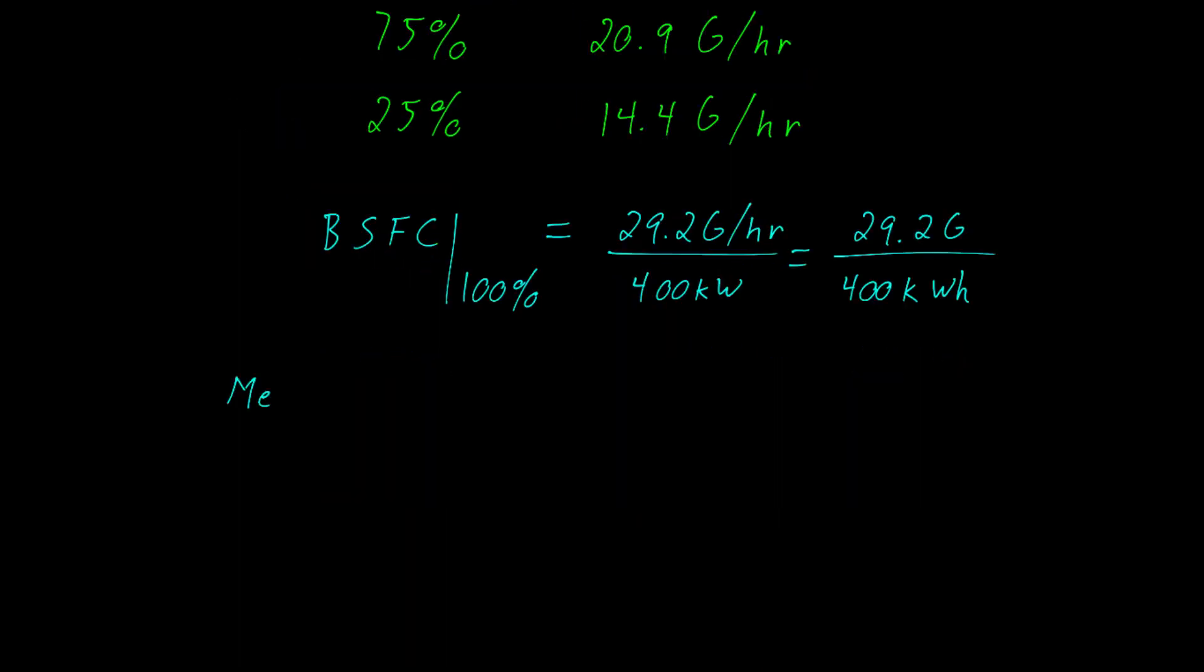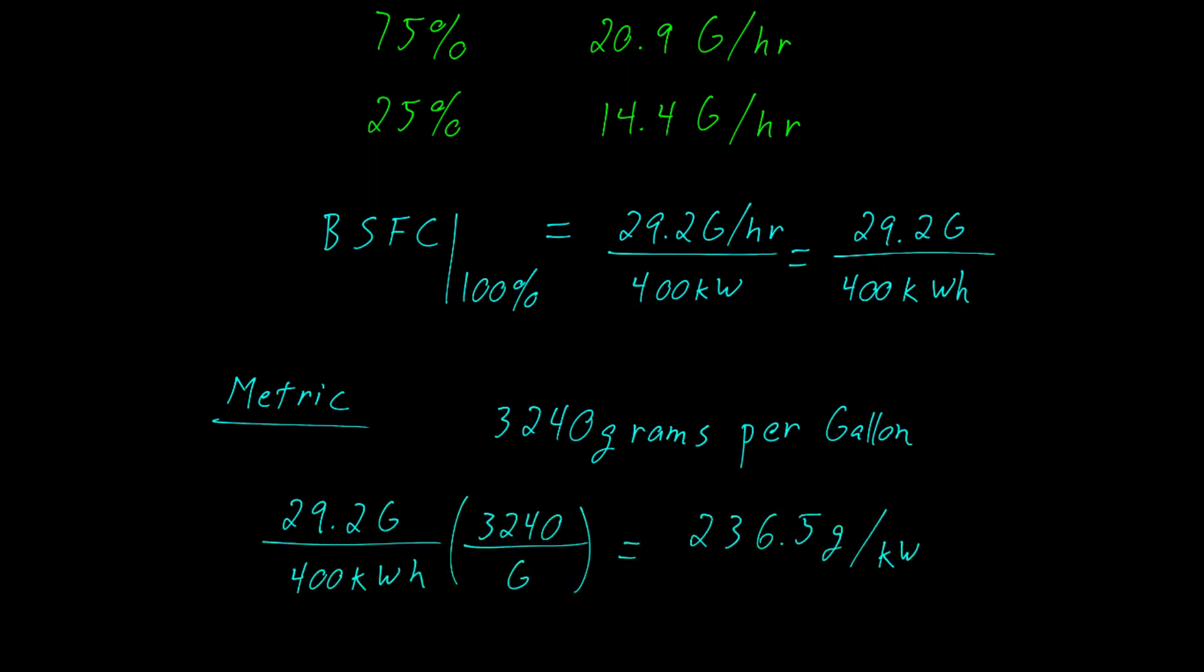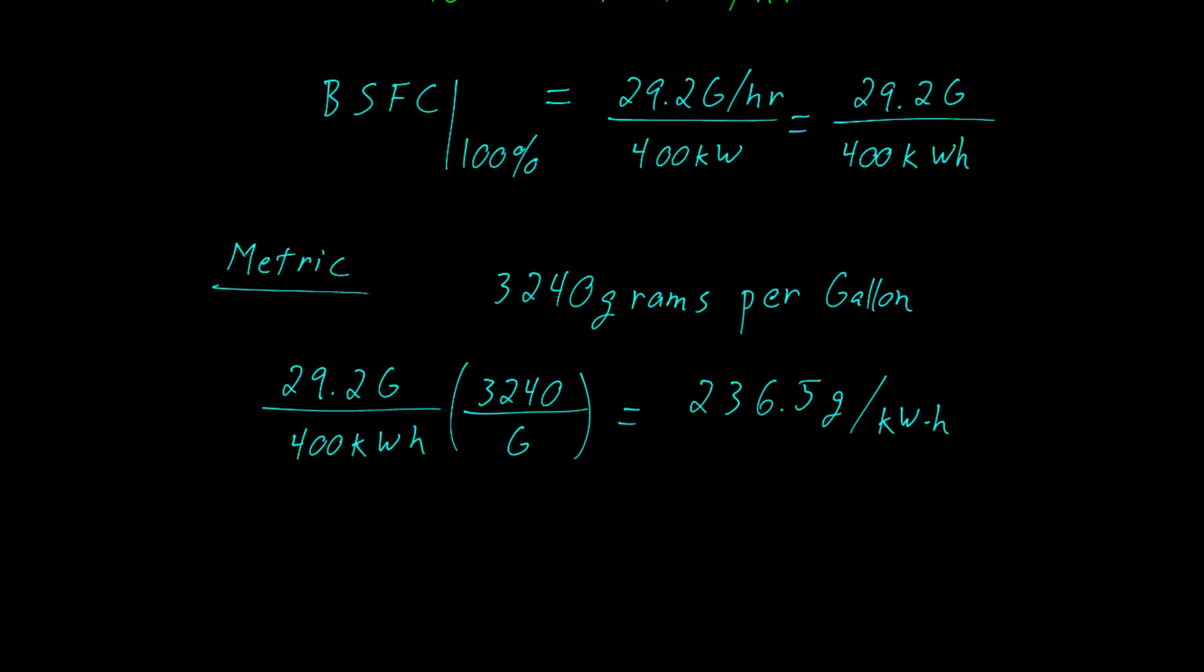Let's convert the numbers into metric. To do that, we need to know that diesel weighs about 3,240 grams per gallon. And then, using dimensional analysis, we arrive at 237 grams per kilowatt hour. Again, that's for the engine when it's under 100% load.